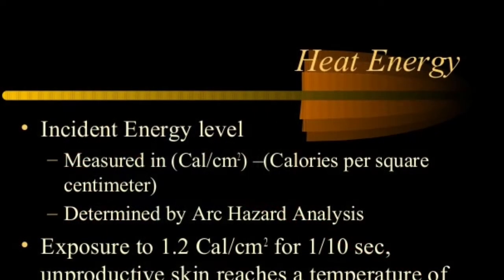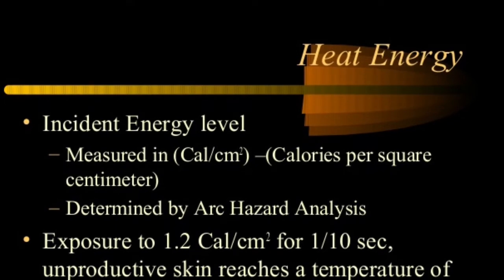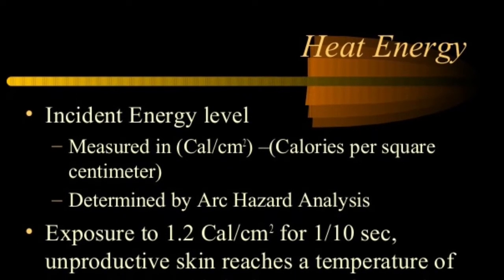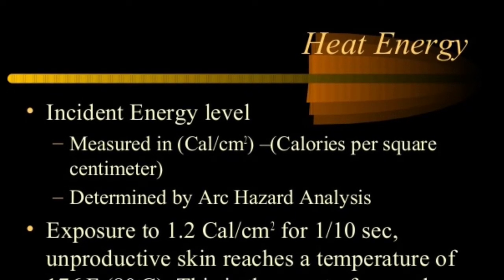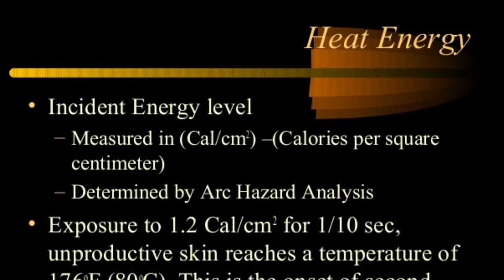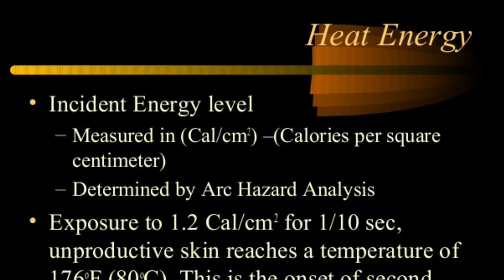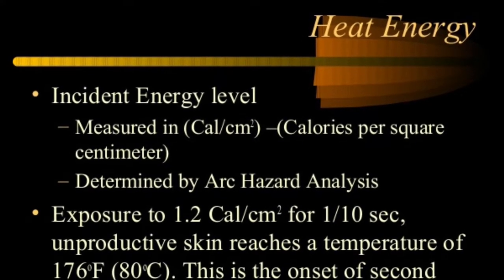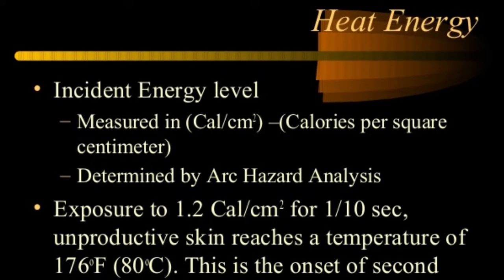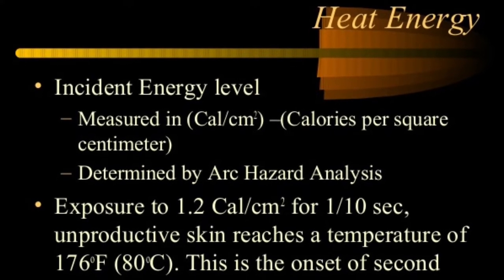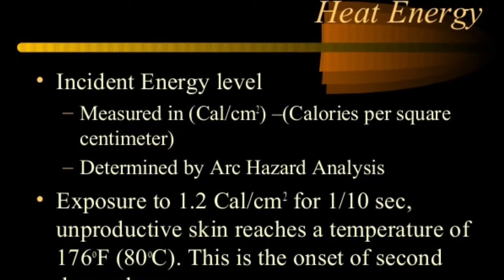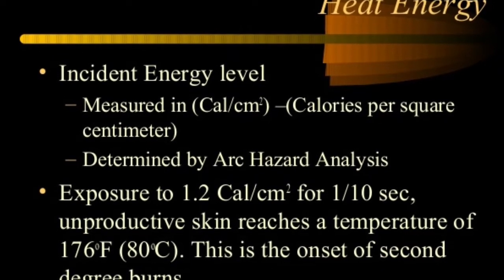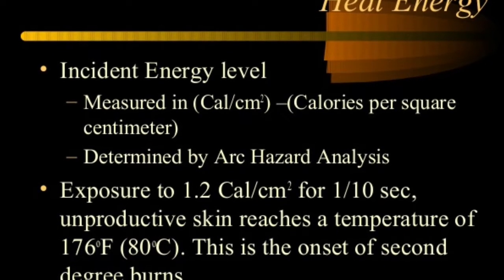Incident energy is the amount of thermal energy impressed on a surface a certain distance from the source generated during an electrical arc event, typically expressed in calories per square centimeter. Predicting the amount of available incident energy is crucial in selecting appropriate PPE. Properly rated PPE prevents injury from melting or burning clothing or from direct skin exposure due to the increased temperature during an arcing fault.